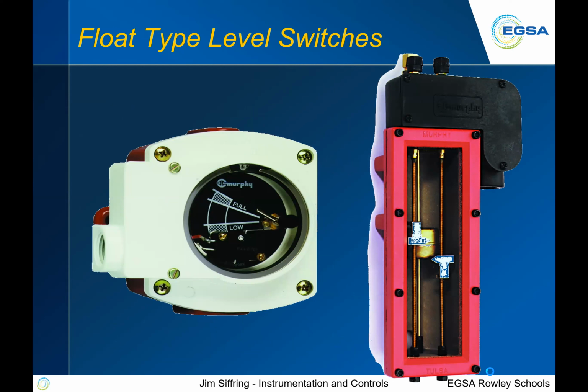More float type switches: the Murphy switch gauge, very common in the industry. Basically there's a float inside this device. On the left-hand side, there's a pipe fitting. You'll tie that into, say, a radiator connection, or into a radiator or something. Set it to where this device will be at the level that you want that tank to be set at. Then there's a float inside there. When fluid comes in, it floats the switch, and you'll see metallic contacts in there that give us a signal out. The right-hand one is a very similar type device and does pretty much the exact same thing.